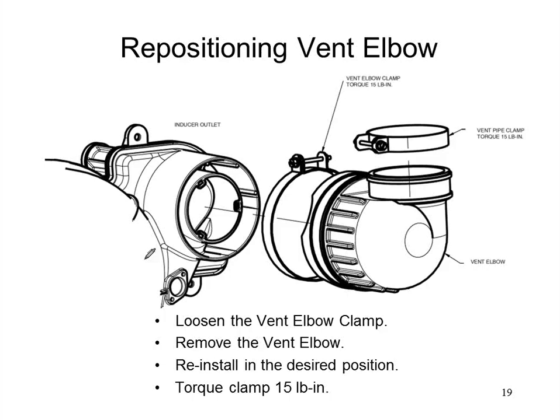This is a blow-up of what that venting elbow looks like. So like I said, all you have to do is basically loosen up this clamp, which looks like a radiator hose clamp, and then you can rotate this entire assembly 90, 180, or 270 degrees to vent it the direction you want. There's another clamp on the other side of it over here that clamps onto your PVC pipe going out of the unit.